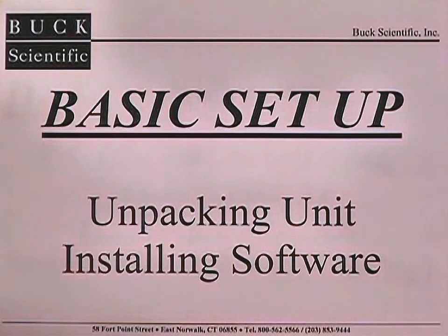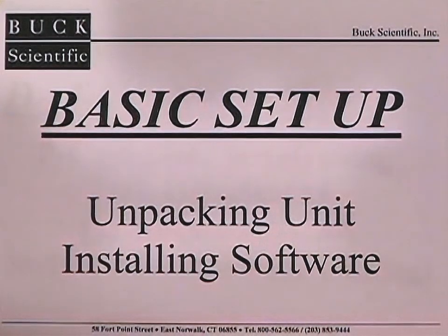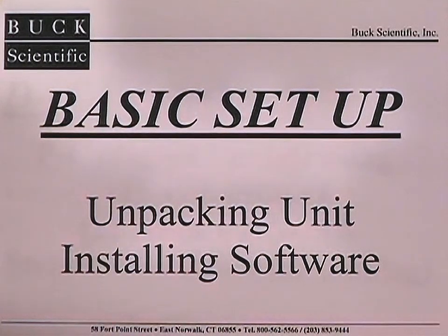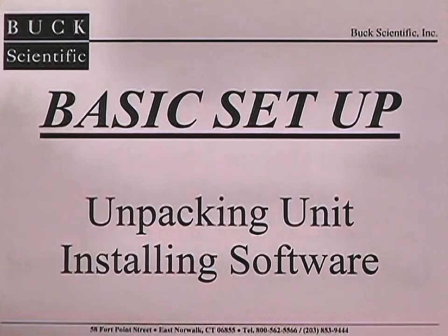The Buck Scientific M500 is shipped with the optical components locked down and protected to avoid potential damage in transit. These lockdown devices must be completely removed prior to plugging the instrument in, otherwise damage to the mechanical assembly can occur. The customer is responsible for the final installation of whatever software package is purchased with the M500, and Buck Scientific cannot be responsible for any incompatibilities with their software or operating system.